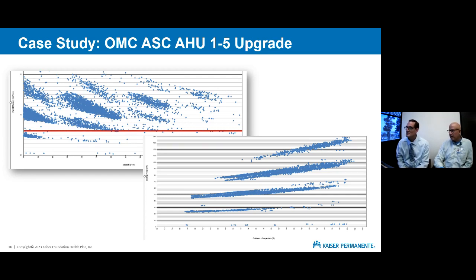And so we started looking at this, we got together and looked at this as a team, and with an EER of 6.577, you can't achieve 0.8 kW per ton. The math actually comes out to 1.82 kW per ton.